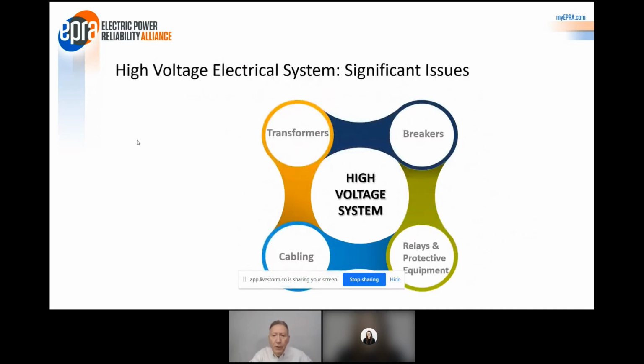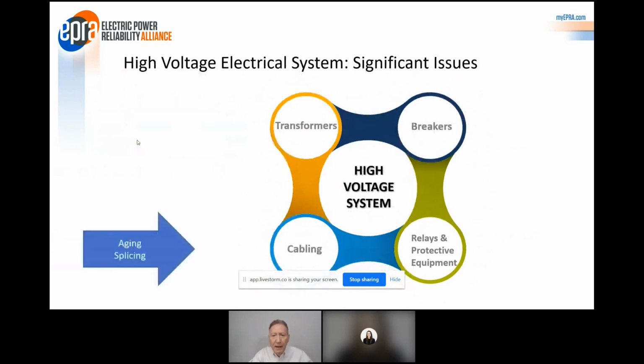When you look at the significant issues with each of these: transformers have not been maintained. You get dirty oil with moisture in it. The majority of transformers that one of our members tests - and they test over 100,000 industrial and commercial transformers a year - have unacceptable levels of moisture. Think about that. It's poor maintenance; you need to get the moisture out. Moisture kills the paper, and the life of the paper is the life of the transformer, et cetera.